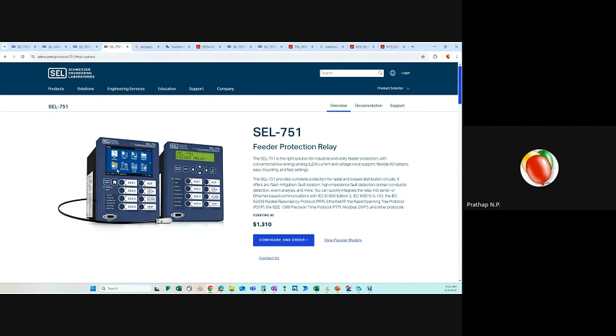So let's say if you have a flash of light and also you have high current over a threshold, then you can AND that logic, right? The digital bit coming from this sensor and the digital bit for overcurrent can be used together in a logic to determine there is an arc flash event, and you can trip immediately. That was not at all possible back in the 60s. And again, this is in addition to all the other conventional protections that you would have.